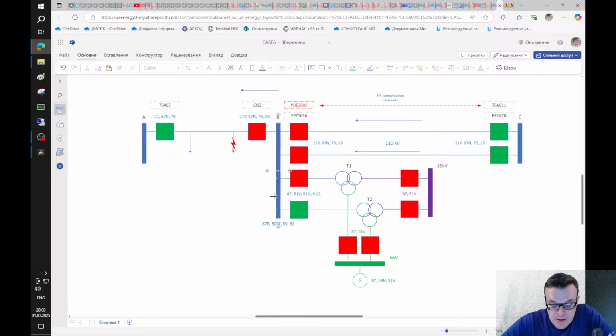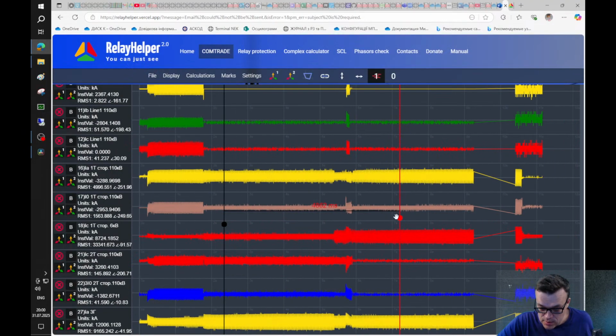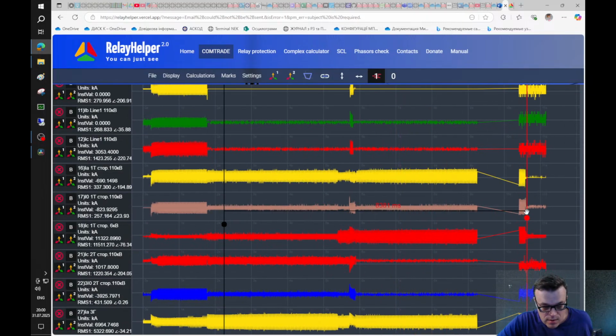So at power plant B, not only did this protection fail to operate, but also some of the functions of transformer 2 and transformer 1, because during that period of time the ground overcurrent protection should work on both transformers. And here we can see the first transformer's zero sequence current and phase current. At this point they became 0. The current of the generator decreased. So at this point this circuit breaker was opened.